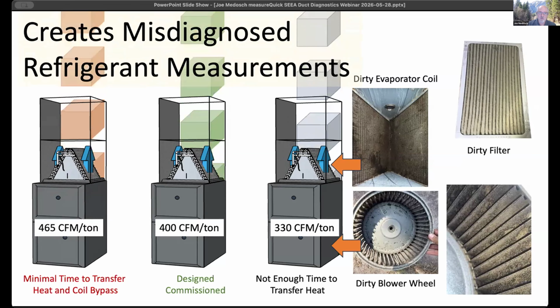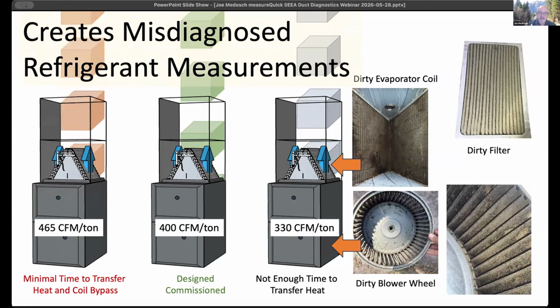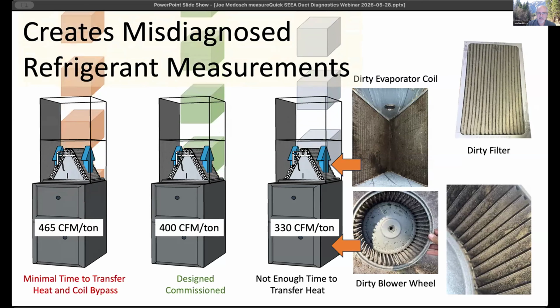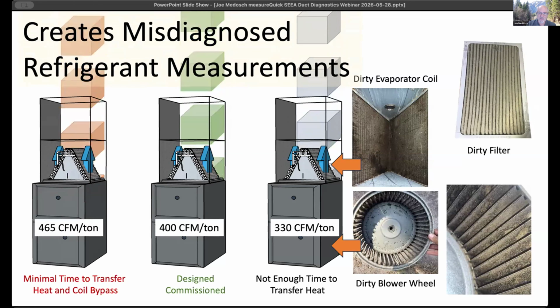So in general, these can create misdiagnosed refrigerant measurements outside. I may have a really low superheat or my subcooling could be off. There's a variety of conditions that would show up in my pressures and temperatures outside, at the condenser, that are really caused by airflow problems inside. So we want to remind you to be cautious about just adjusting the refrigerant to confirm whether the system is operating correctly without doing proper visual diagnostics and measurements of actual airflow.